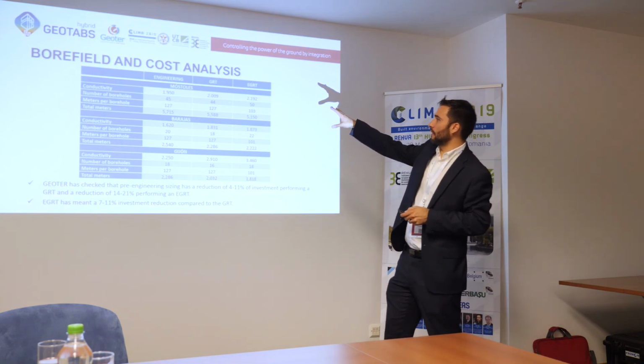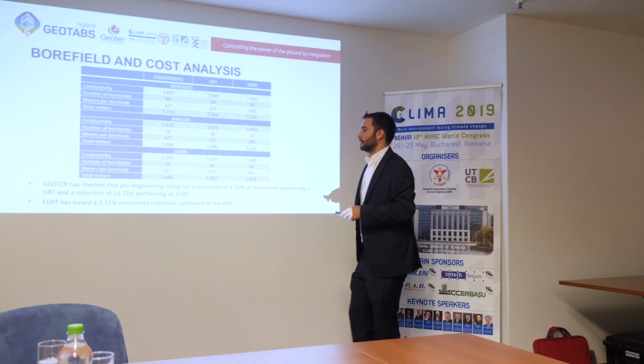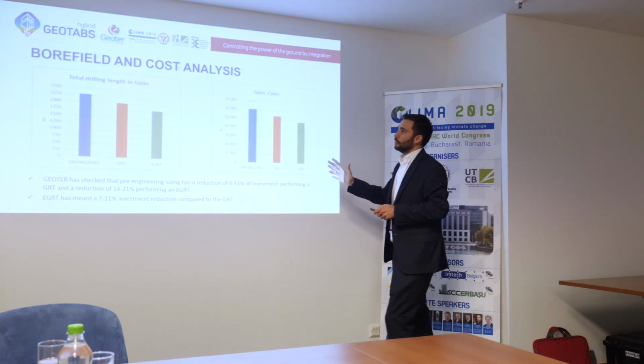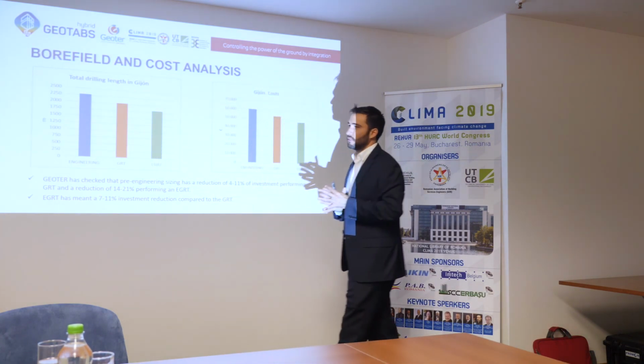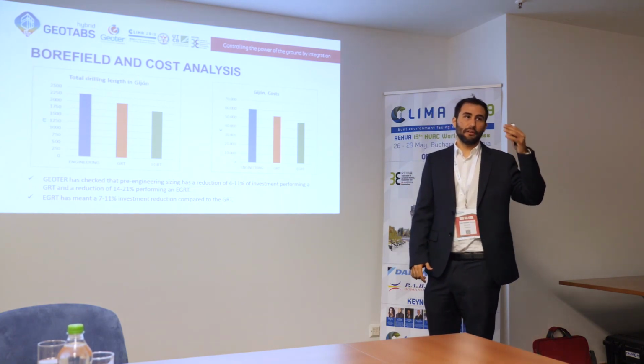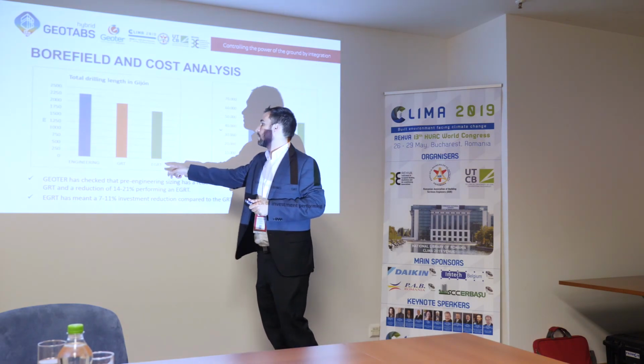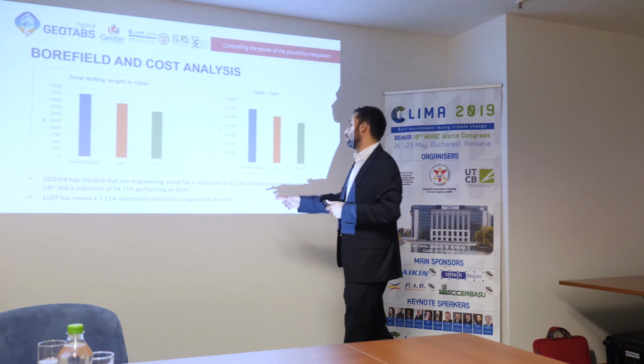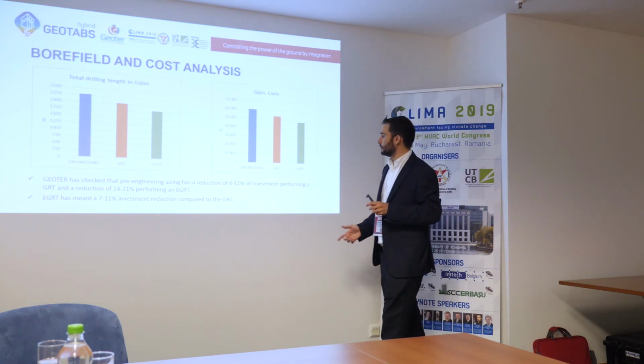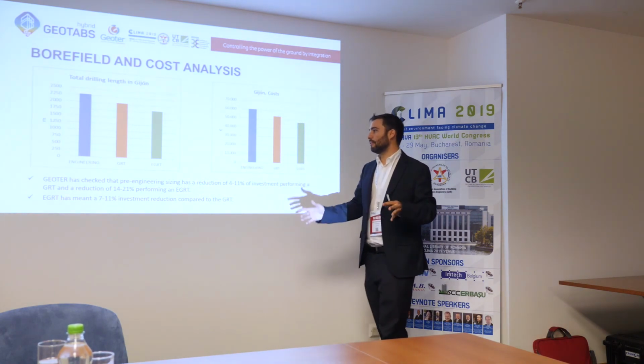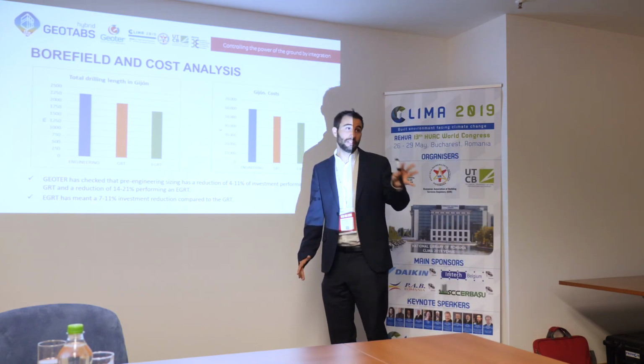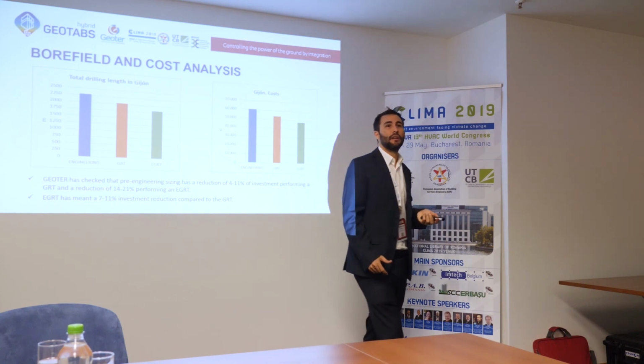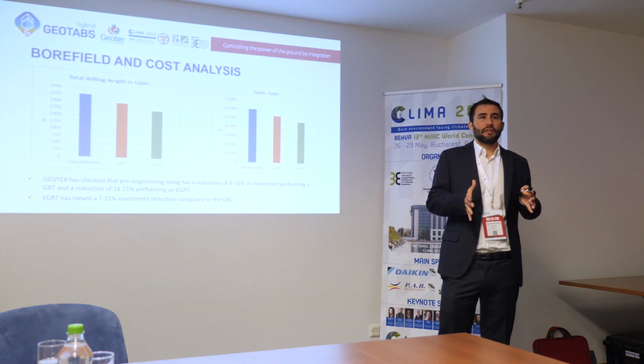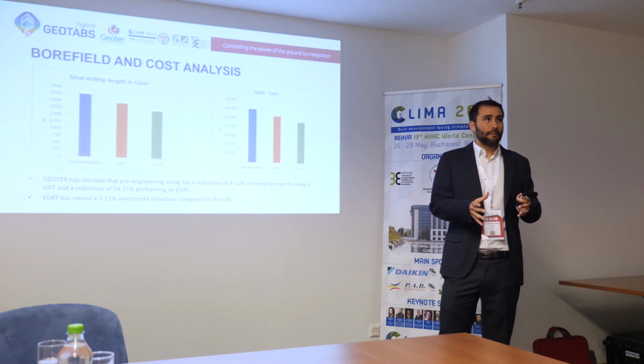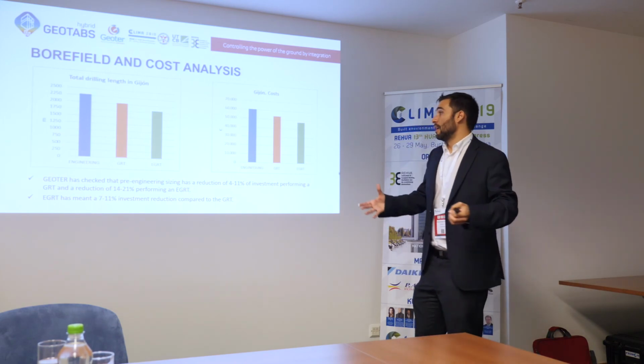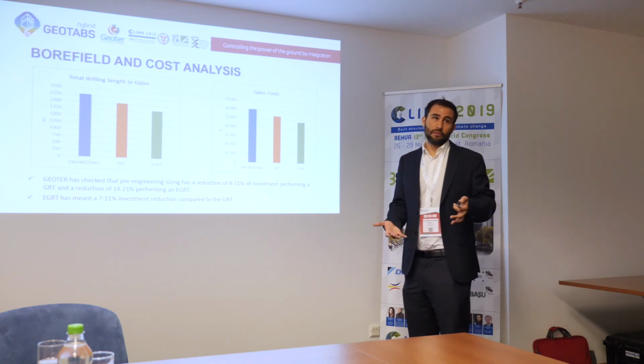So this is in the three cases, Móstoles, Barajas, and Gijón, and we can see the differences, for example, of Gijón here. We can see that if we size the borehole field only with engineering knowledge, with geothermal response test knowledge, and with enhanced geothermal response test knowledge, we have checked that we have a reduction of 11% performing a GRT, and a reduction of around 14-21% in meters to drill performing an enhanced geothermal response test. So with the enhanced geothermal response test, we can reduce the meters to drill, only improving the design of the borefield. So we reduce the initial cost, which is very important.